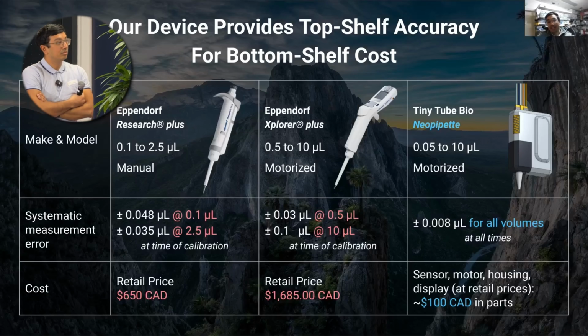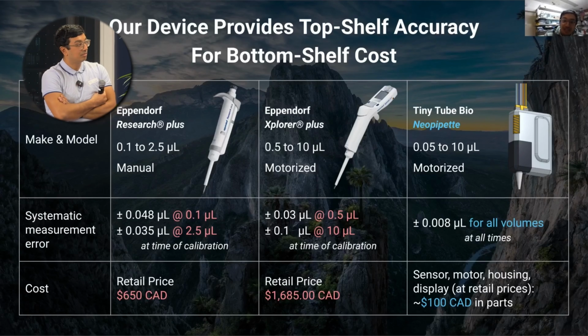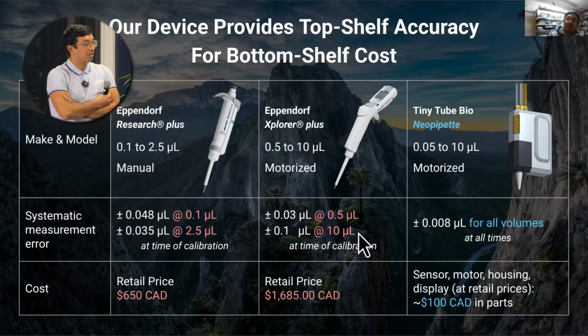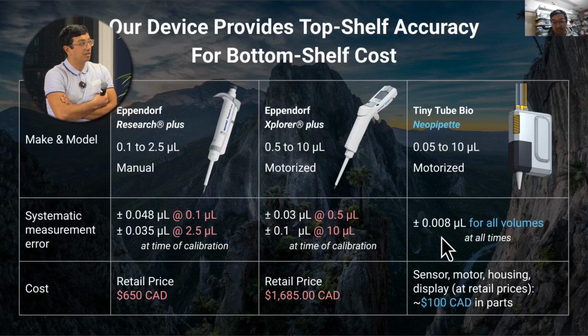So here are some specs. We have the Eppendorf motorized pipette here, and these are its official stats, which would happen at the time of calibration. So it's plus minus 30 nanoliters at a 0.5 microliter target volume, and it's plus minus 100 nanoliters for a 10 microliter target volume. Using our sensor, we can make a pipette that goes to 10 microliters that has a plus minus 8 nanoliter volume at all times. Not just at time of calibration.